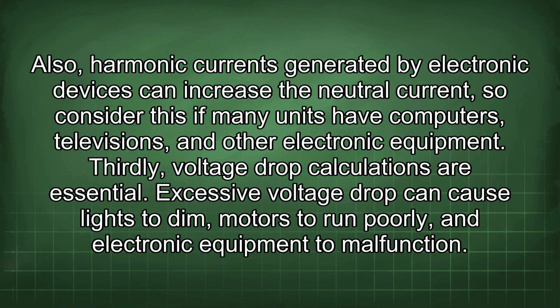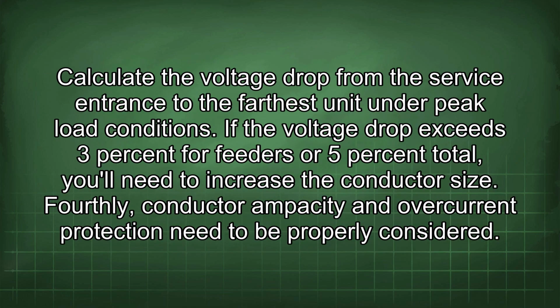Thirdly, voltage drop calculations are essential. Excessive voltage drop can cause lights to dim, motors to run poorly, and electronic equipment to malfunction. Calculate the voltage drop from the service entrance to the farthest unit under peak load conditions. If the voltage drop exceeds 3% for feeders or 5% total, you'll need to increase the conductor size.